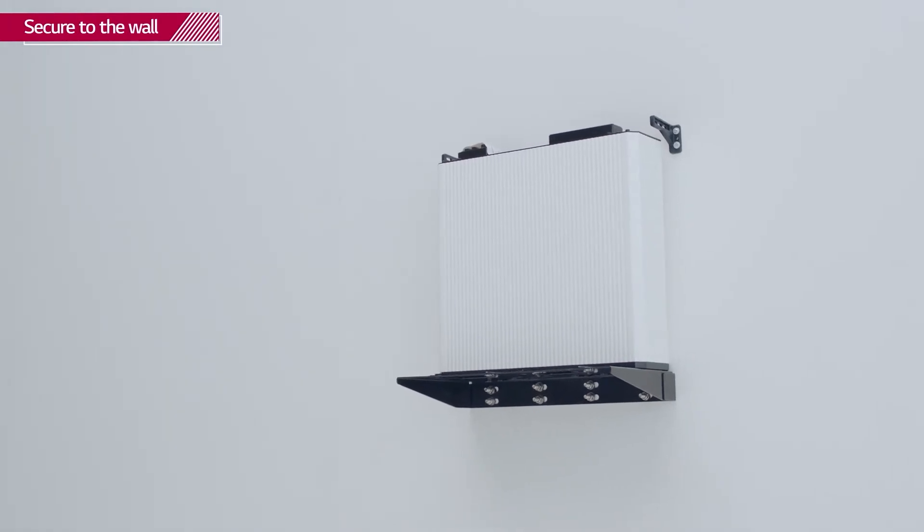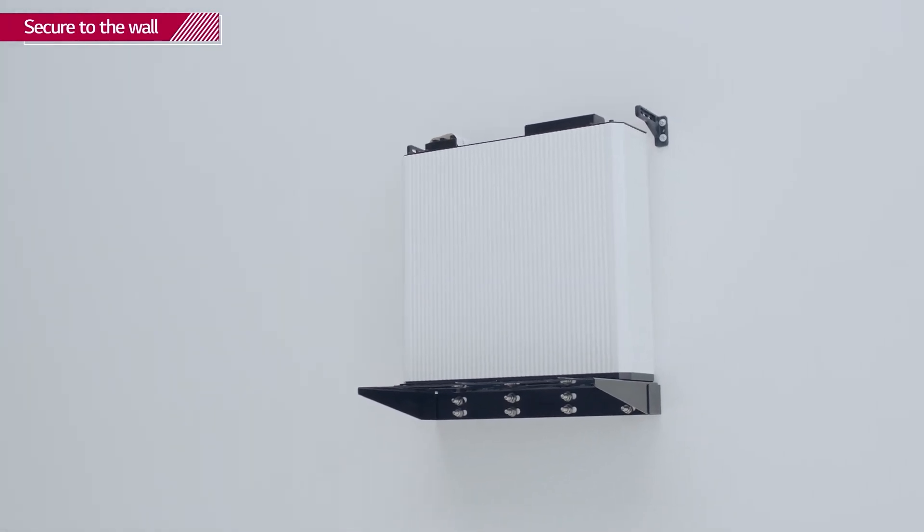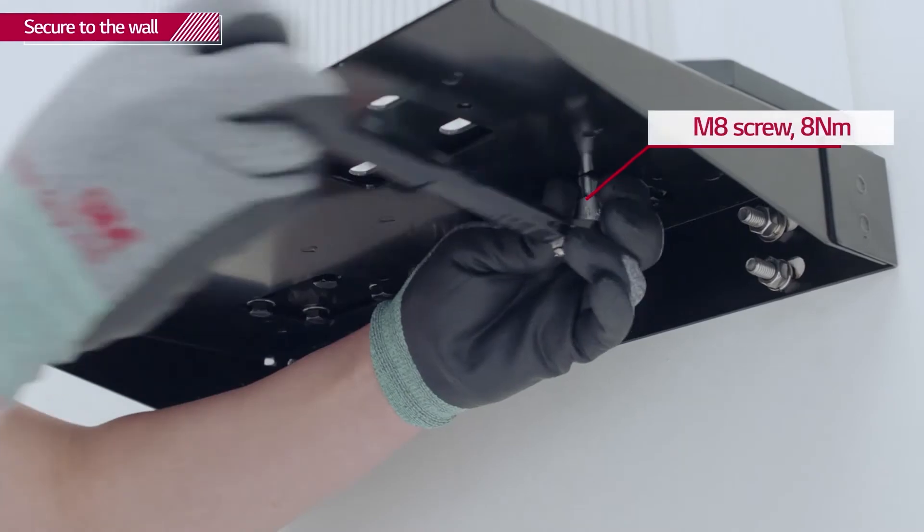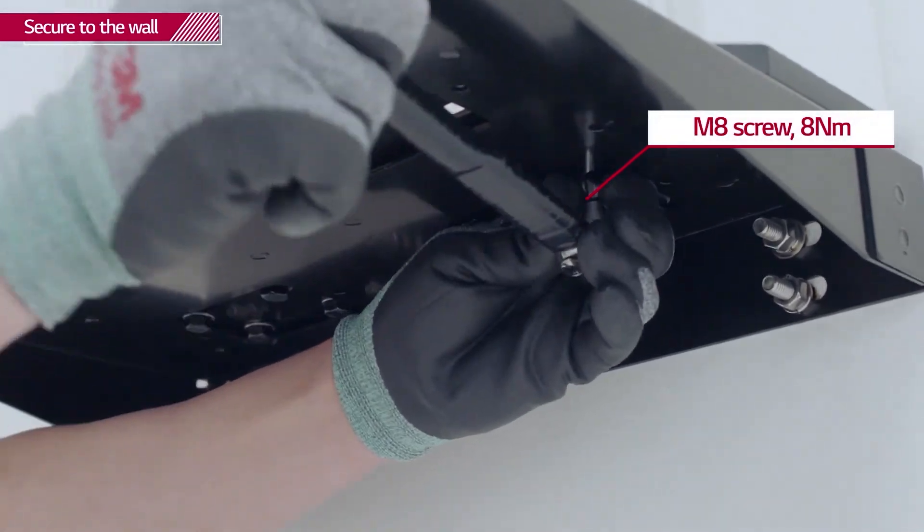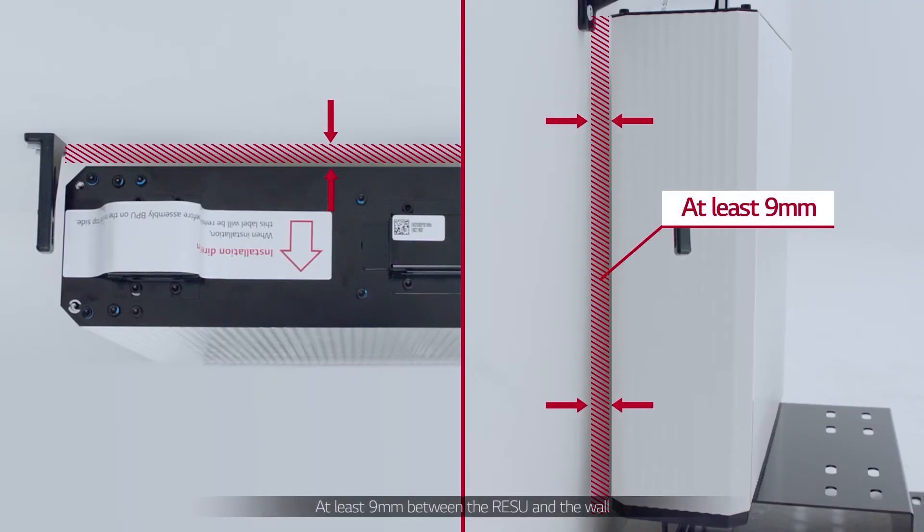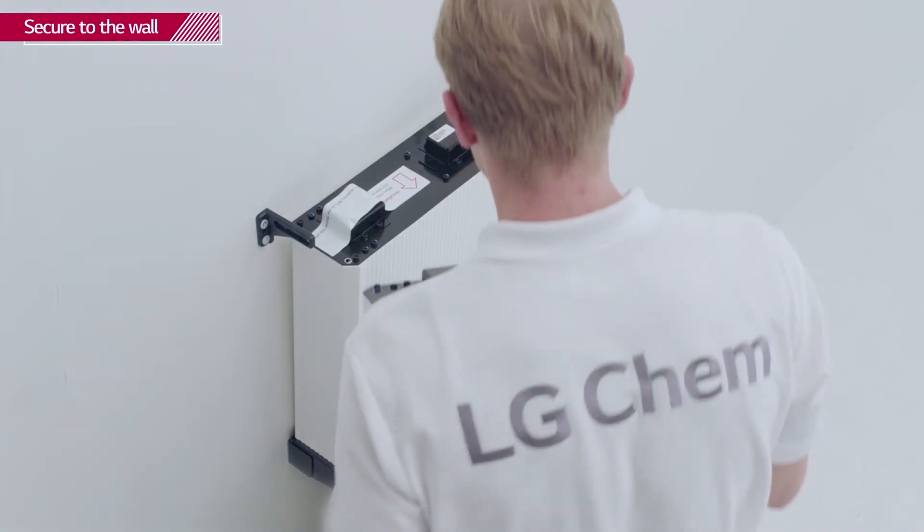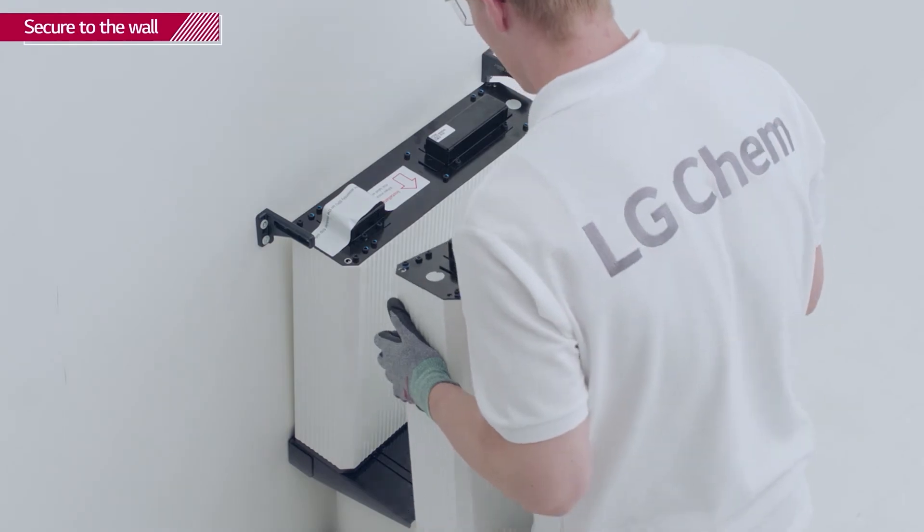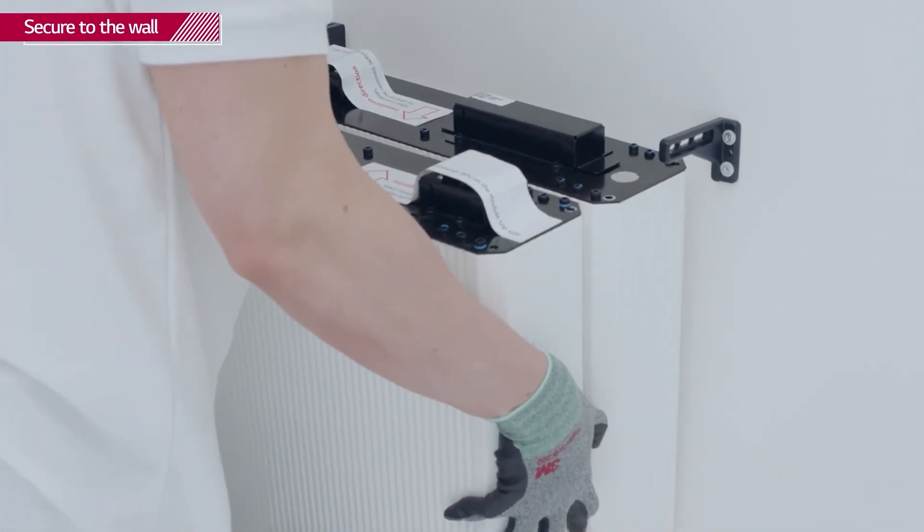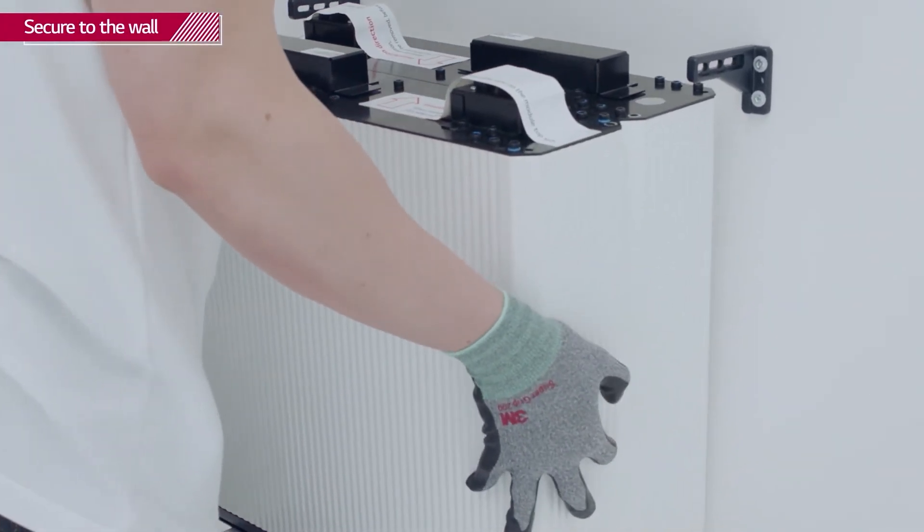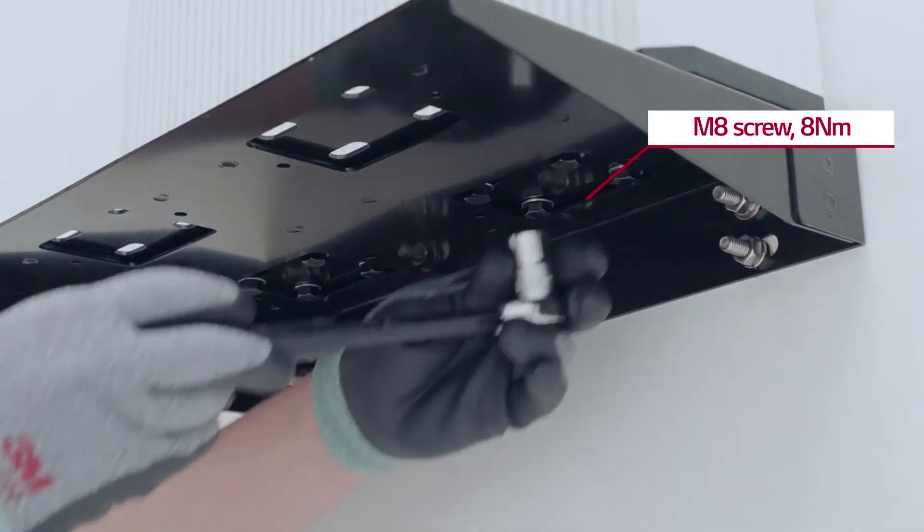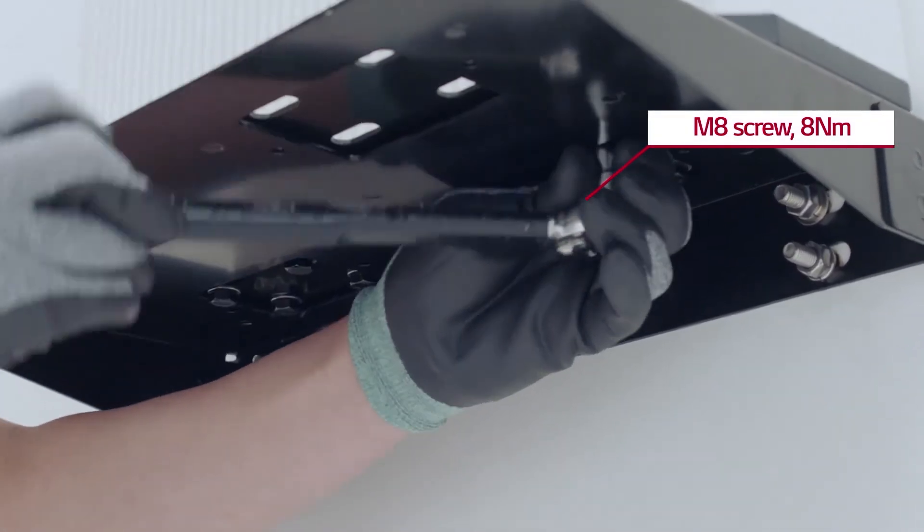Place the first battery module on the wall mounting bracket and fasten with an M8 screw with a torque of 8 Nm. Just like the first battery module.